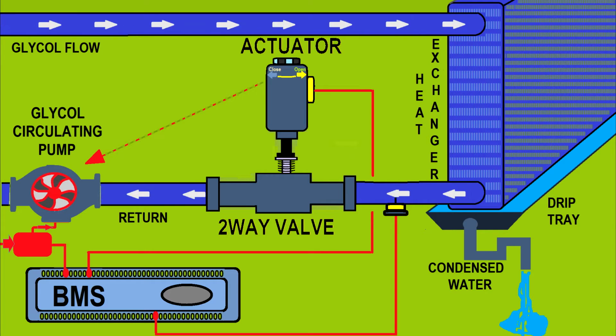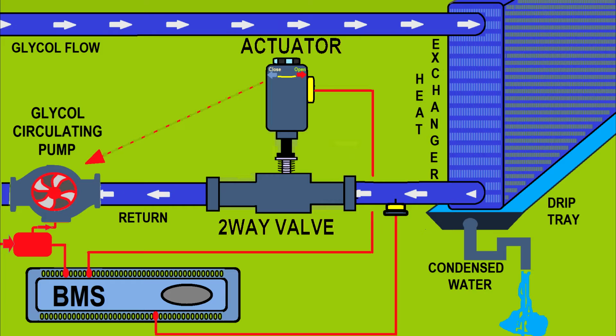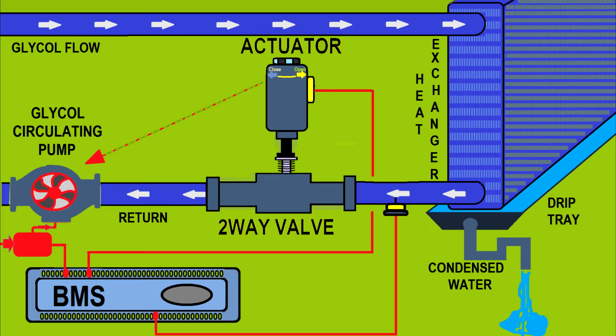Now usually in this situation, if you don't have the balancing valve, the balancing valve which short circuits the flow to the return, you'll interlock the actuator, the valve, with the pump, so until the actuator opens 100%, the pump will not run. I found the system pretty inefficient, a little bit pointless.